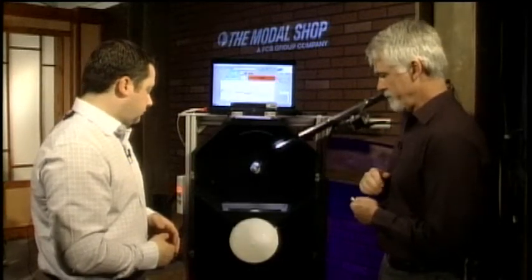So this one is the cracked one. We're looking for changes in the resonant frequency — as you can see, it's out of the green boxes. In the screenshot we see several peaks, and those are the peaks related to that particular device we just ran. We've taught it what should be a good response.